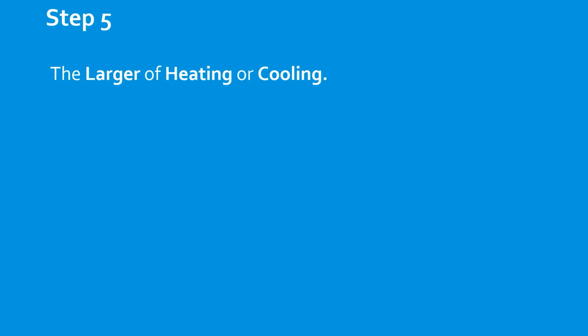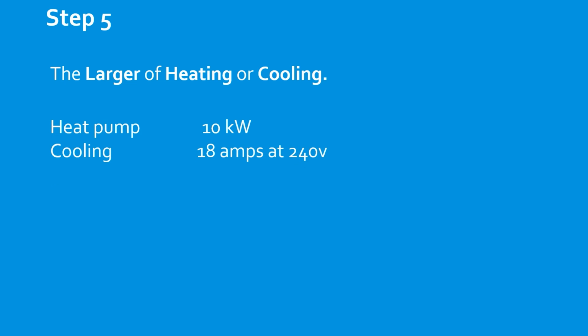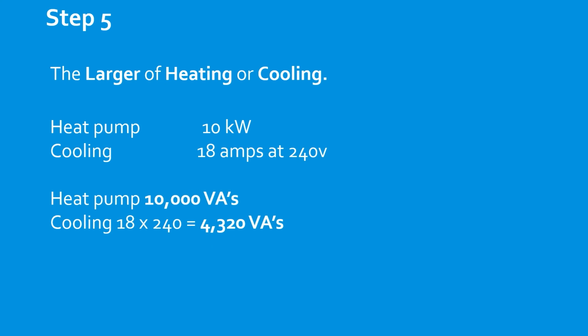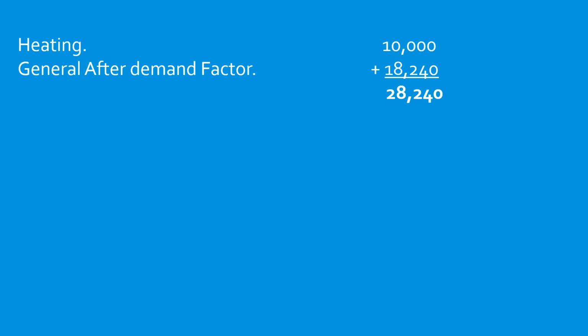Step 5, you do the larger of the heating or cooling. Okay, so we have 10 kW and 18 amps at 240. You can take a guess. It's going to be the heat pump in this case. And we're going to select the larger. Okay, our heating was at 10,000 VAs. Our general, after demand factors, was 18,240. Add them back together. You're going to get 28,240. And you're going to select D.